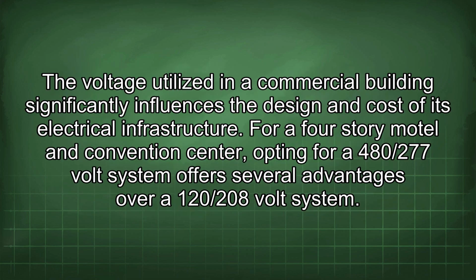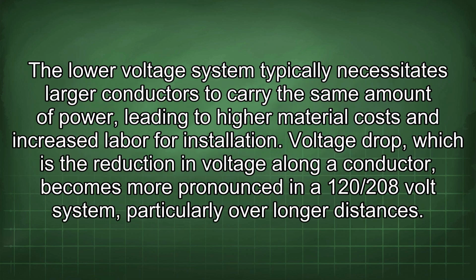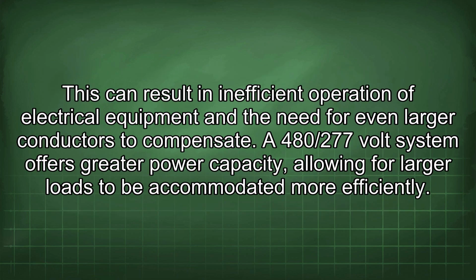The voltage utilized in a commercial building significantly influences the design and cost of its electrical infrastructure. For a 4-story motel and convention center, opting for a 480/277 volt system offers several advantages over a 120/208 volt system. The lower voltage system typically necessitates larger conductors to carry the same amount of power, leading to higher material costs and increased labor for installation. Voltage drop, which is the reduction in voltage along a conductor, becomes more pronounced in a 120/208 volt system, particularly over longer distances. This can result in inefficient operation of electrical equipment and the need for even larger conductors to compensate.